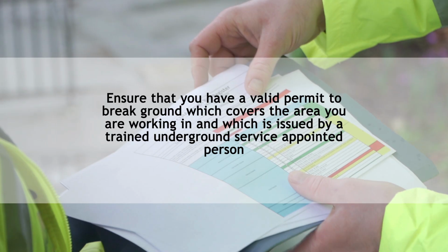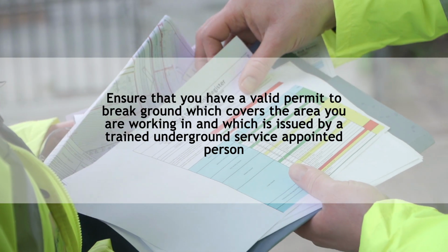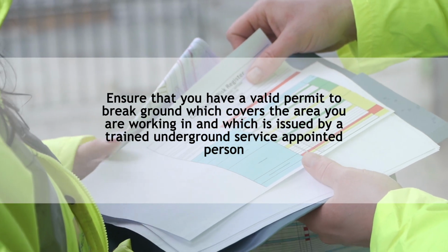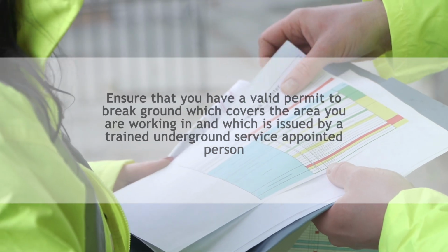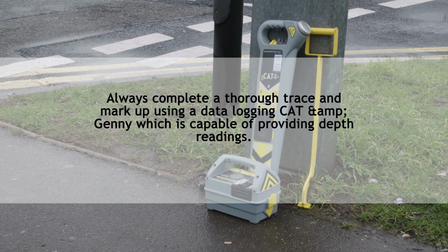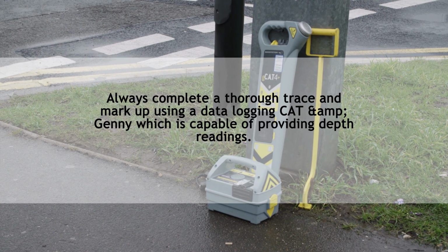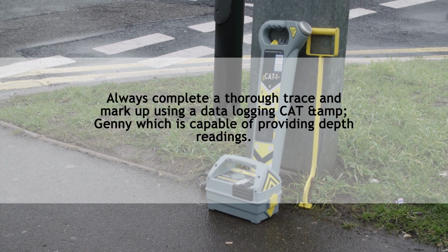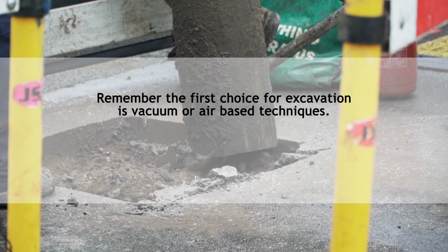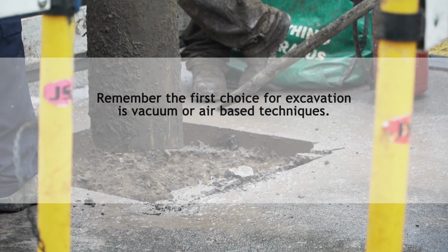Ensure that you have a valid permit to break ground, which covers the area you are working in and which is issued by a trained underground service appointed person. Always complete a thorough trace and markup using the data logging CAT and Genny, which is capable of providing depth readings. Remember, the first choice for excavation is vacuum or air-based techniques.